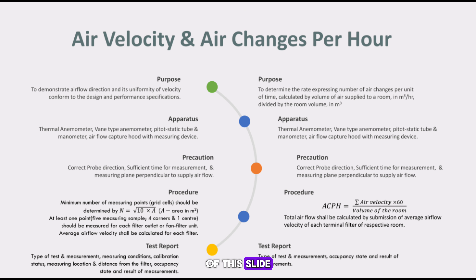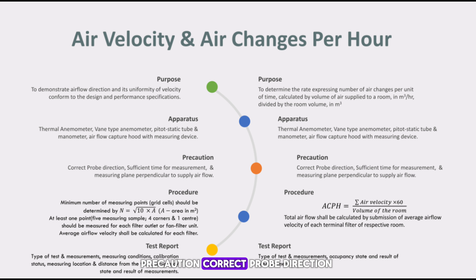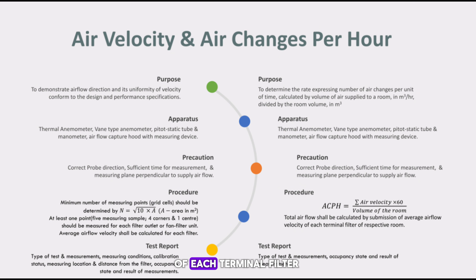Air Changes Per Hour (ACPH) — Purpose: to determine the rate expressing number of air changes per unit of time, calculated by volume of air supplied to a room in cubic meters per hour divided by the room volume in cubic meters. Apparatus: thermal anemometer, vane-type anemometer, pitot-static tube and manometer, and airflow capture hood with measuring device. Precaution: correct probe direction, sufficient time for measurement, and measuring plane perpendicular to supply airflow. Procedure: the given formula is used for measurement; total airflow is calculated by summation of average airflow velocity of each terminal filter of the respective room. Test report includes: type of test, measurements, occupancy state, and result of measurements.